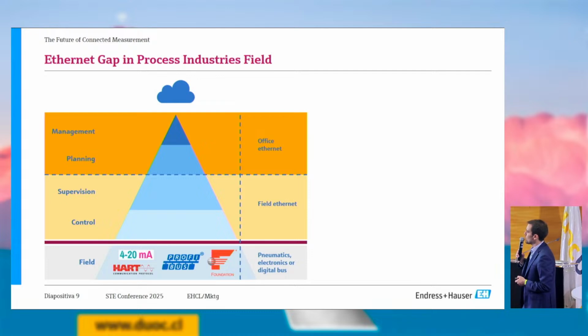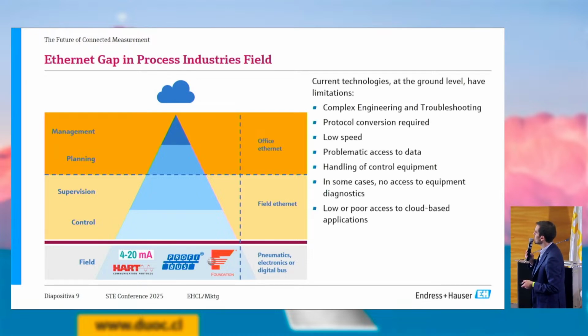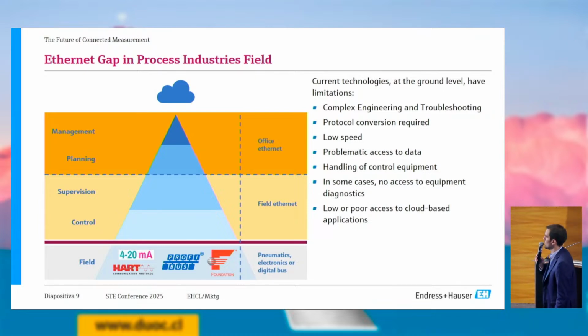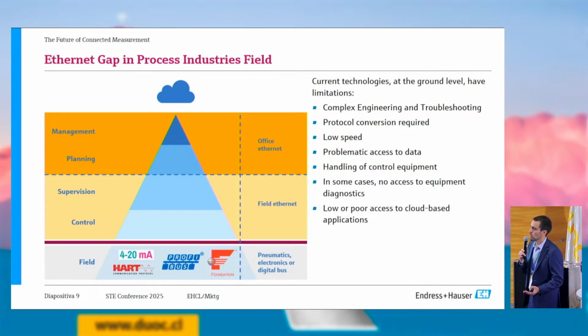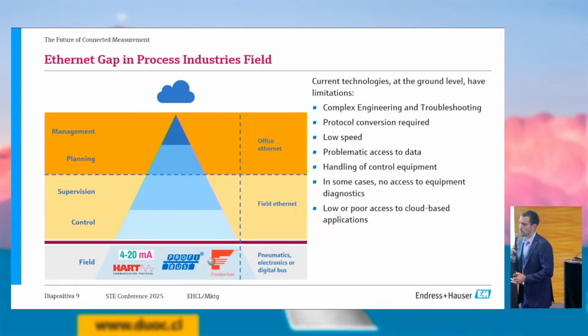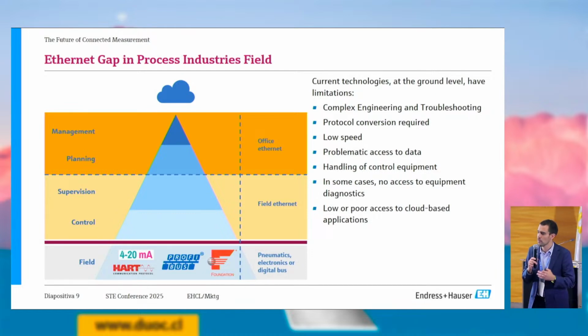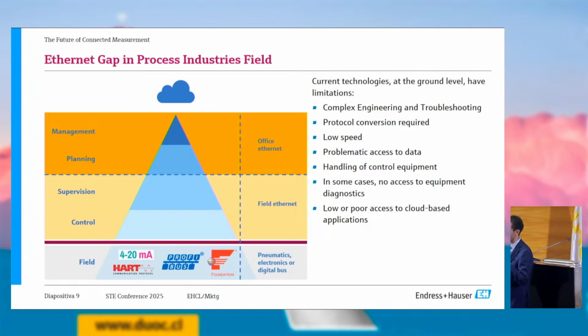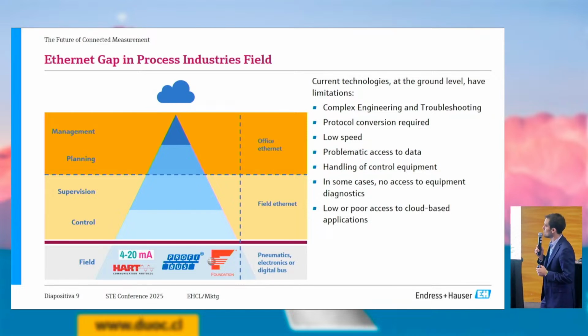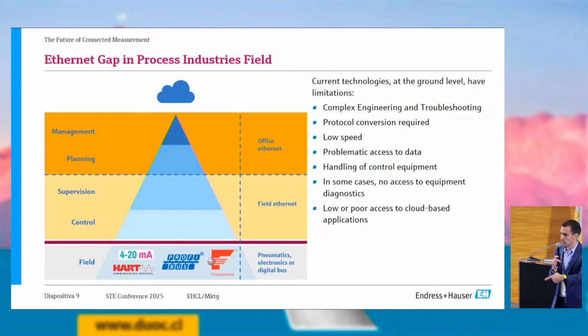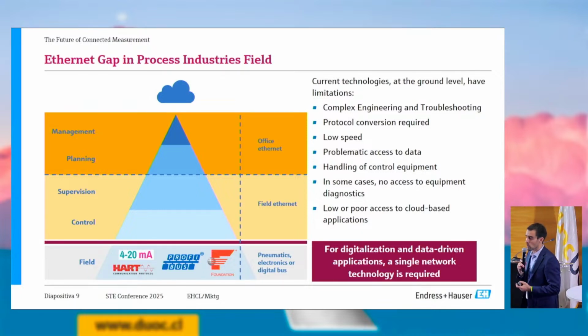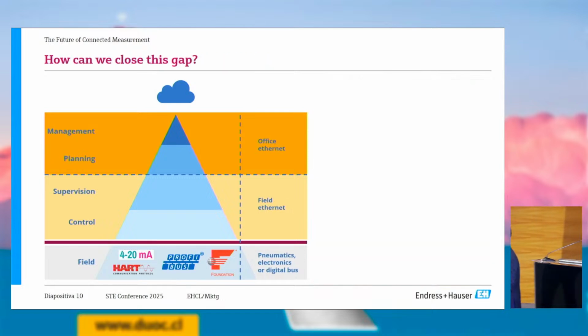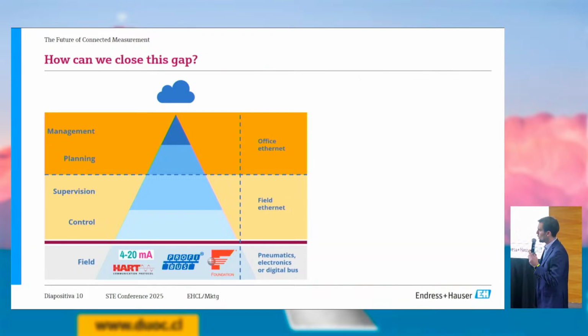There's an Ethernet gap in process industry fields. Current technologies at ground level have limitations, as I mentioned, complex engineering, for example with fieldbus, protocol conversion is required. Many suppliers are now working on developing converters from 4-20 milliamps to Ethernet, from Foundation Fieldbus to Ethernet, and everything at the moment is heading toward Ethernet IP. With low speed for 4-20 milliamps, if you want to digitalize and enable data-driven applications, a single network technology will be required.